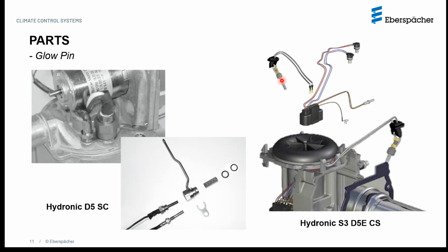Now, in the case of the third generation, they also modified the design. Before, you had to unscrew the glow pin from the fitting in order to remove it, and of course, before you unscrew it, you have to disconnect it from your connector. Over here, you will still have to disconnect it from the connector, but then you can simply pull the glow pin off without having to unscrew it. It is just placed into position, and the grommets that you see on the glow pin assembly locate the glow pin in the right position. So you don't have to use any special wrenches, and when assembling it, you don't have to worry about tightening torque. So it's easier to work with, if you may.